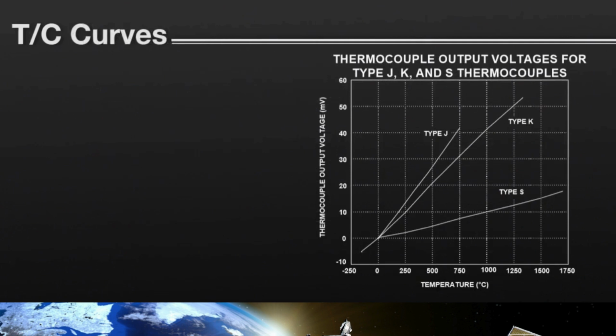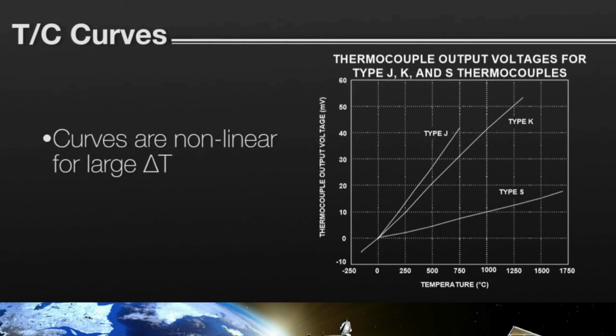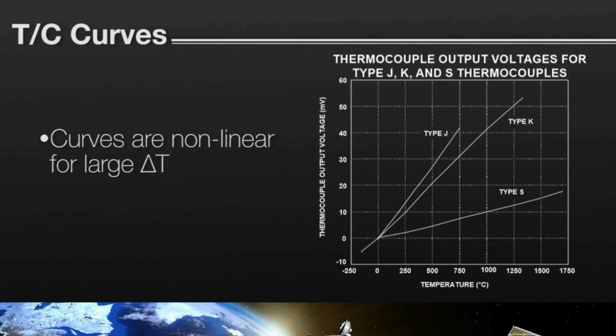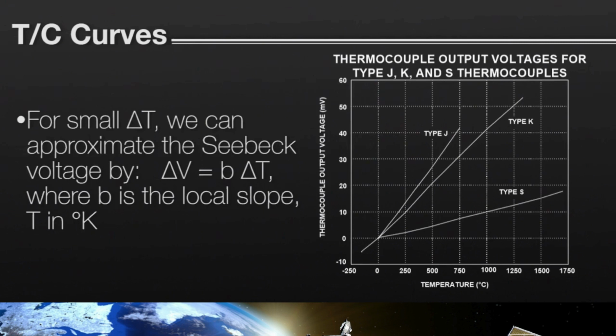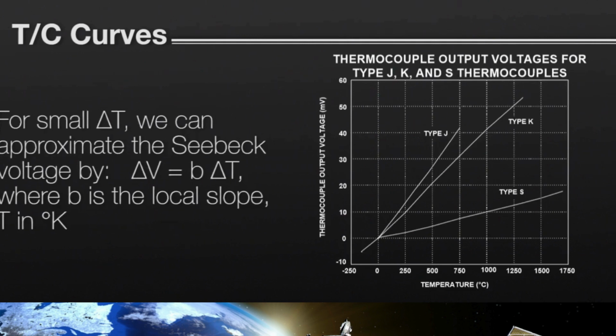Here's some thermocouple voltage curves for types J, K, and S. Thermoelectric voltage versus temperature curves are nonlinear, and you get small negative readings at the very cold temperatures. You can assume linearity for small changes in temperature by using the slope B of the nonlinear curve at the local temperatures. If you do this, though, make sure you do your calculations in degrees K, or you're gonna get into trouble with signs for temperatures below 0 degrees C.